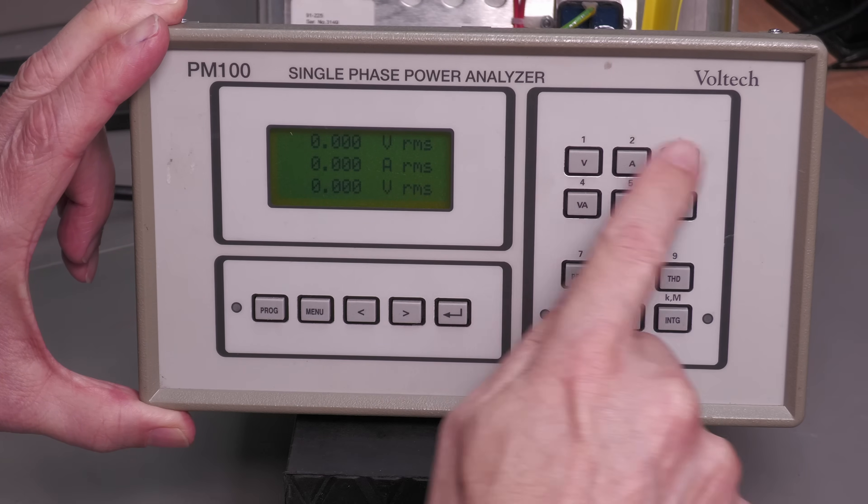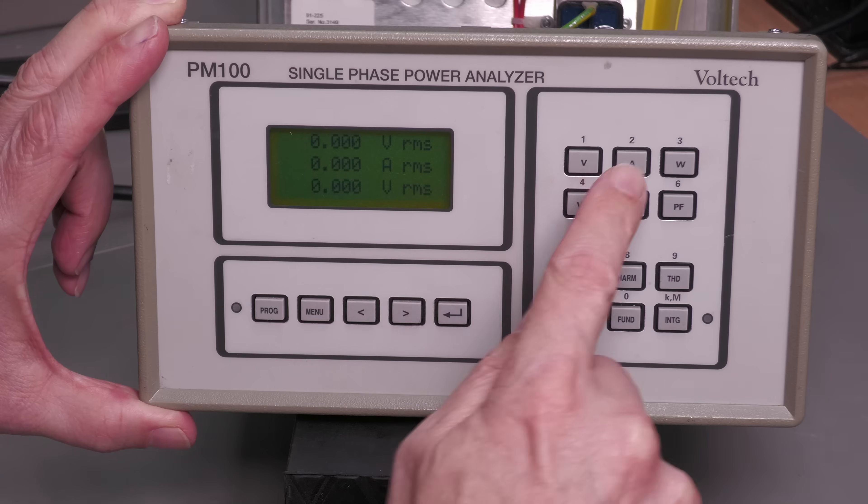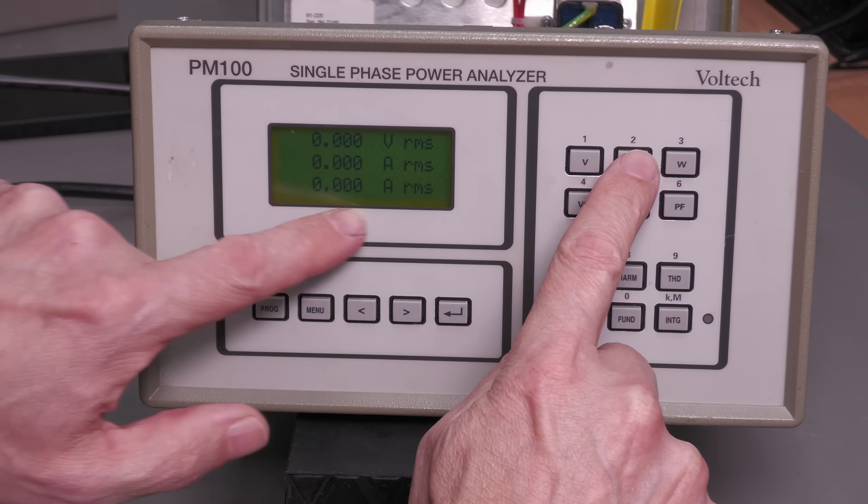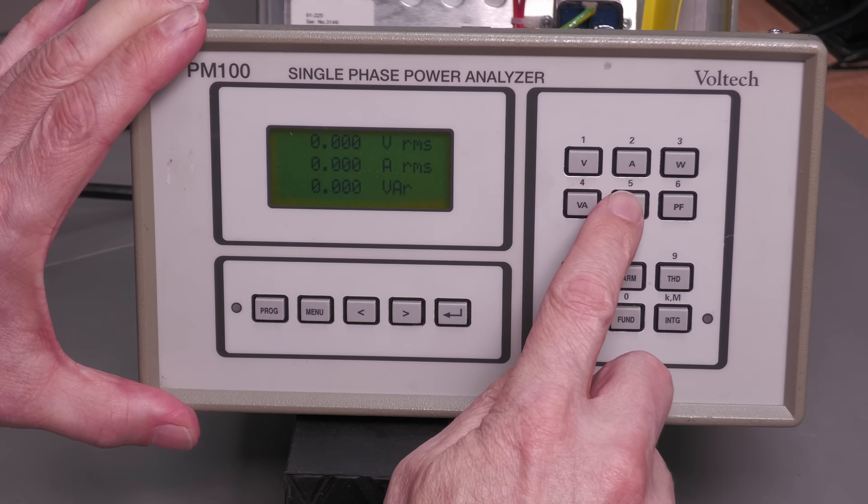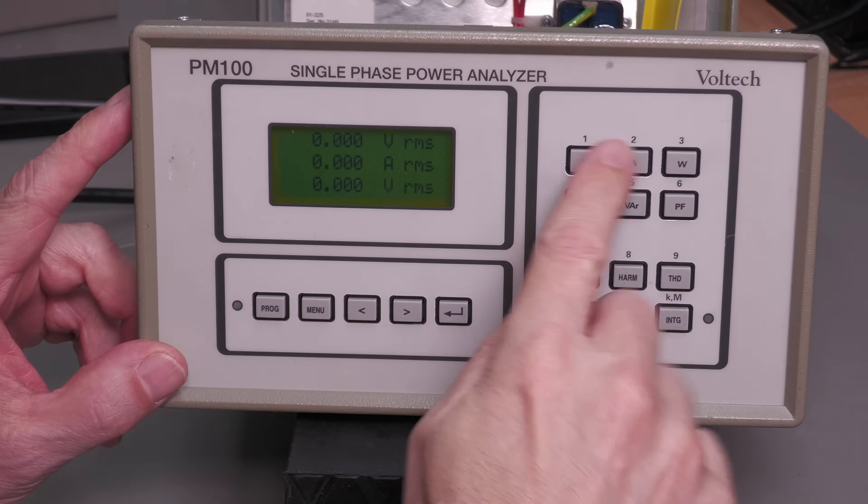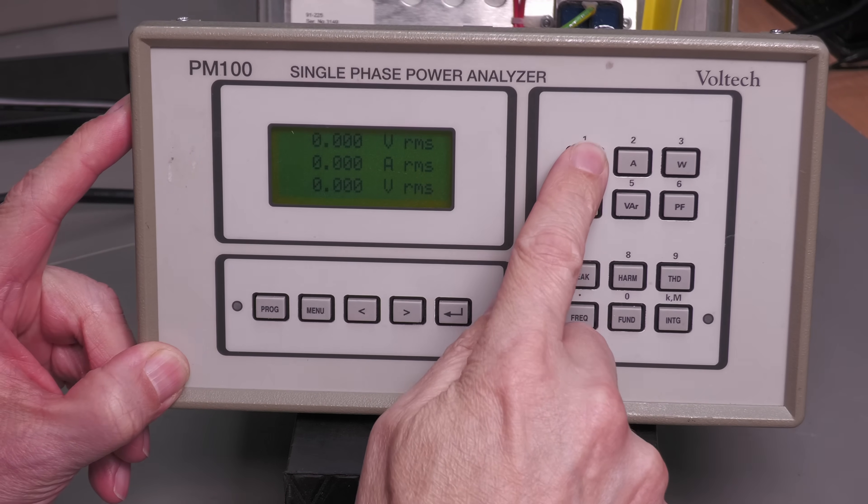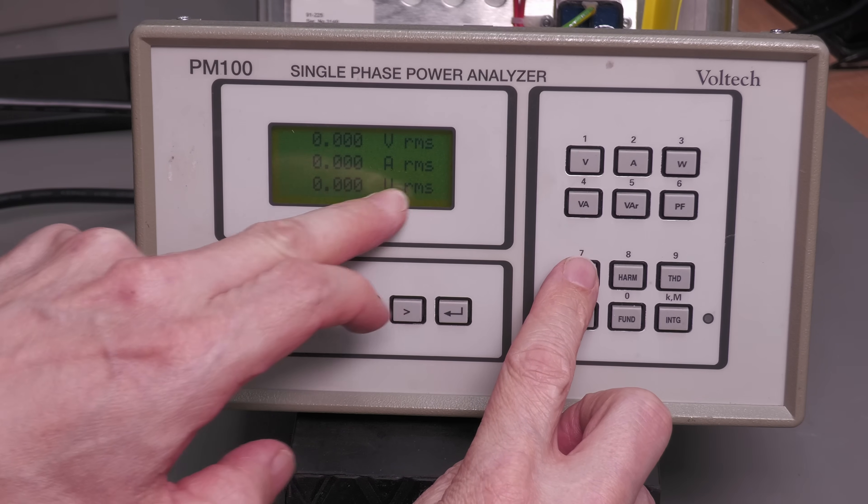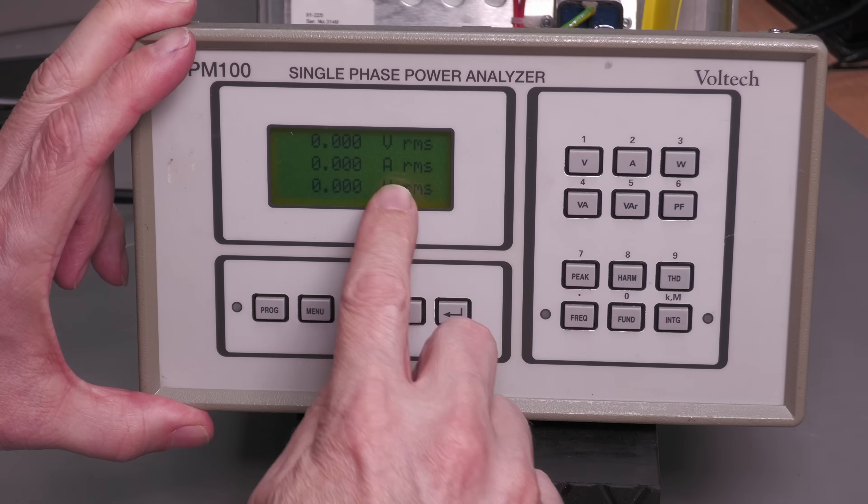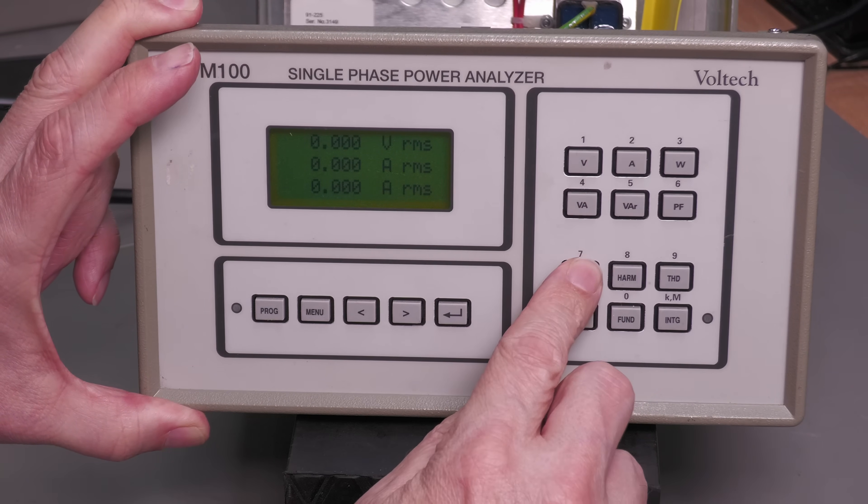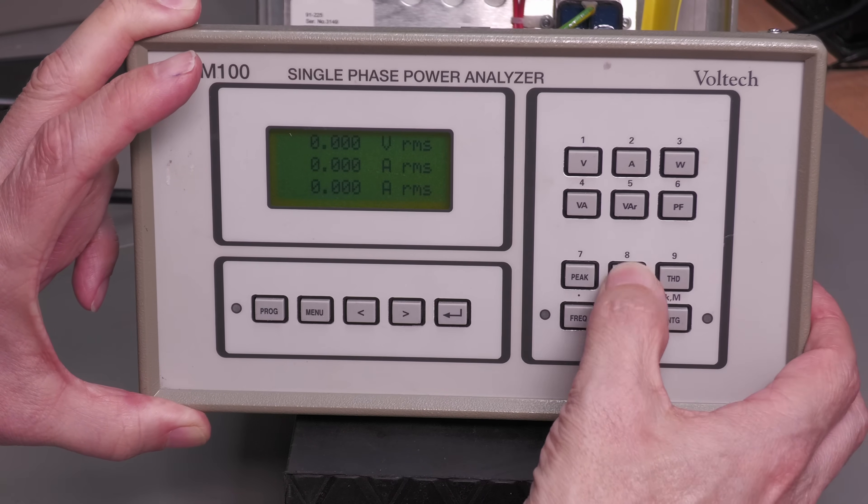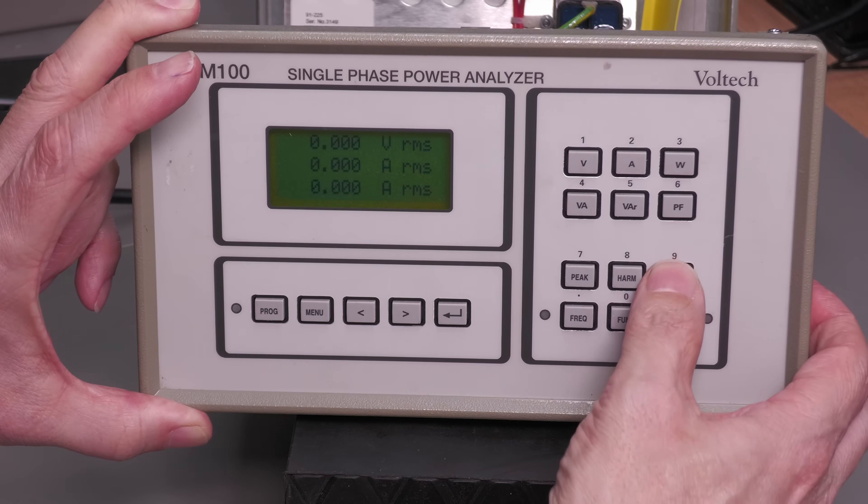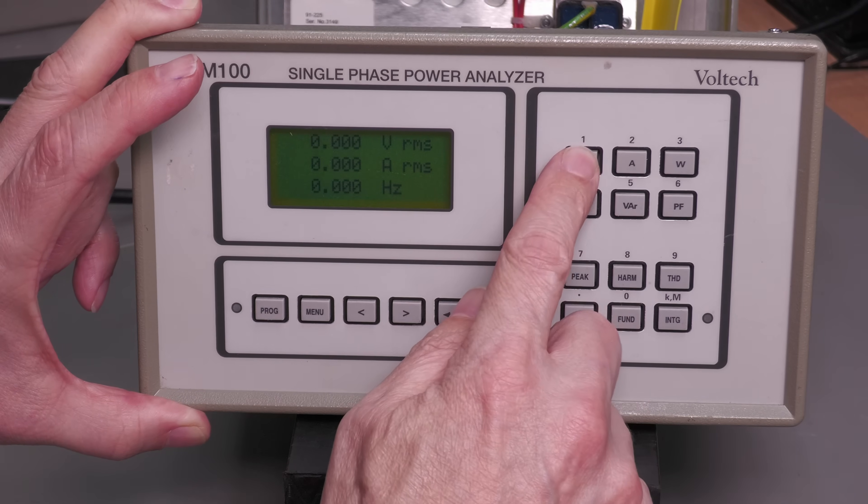So when you press any of these buttons here, you're actually affecting this bottom line here. So volts displayed there, yep, amps, watts, VA, VAR, power factor, that's all correct. And this bottom set here, oh let's just select volts again. That peak button's not working. It should be changing this bottom line here for volts peak. And if I go into amps, it should now change to amps peak. That button's not doing anything. The harmonics nothing, THD nothing. Well, frequency button's working.